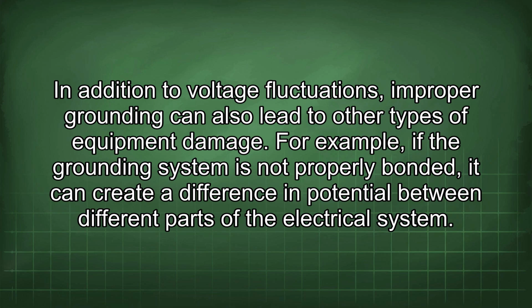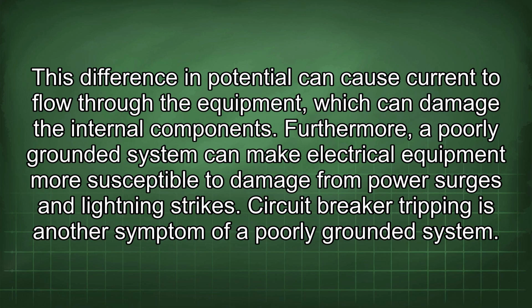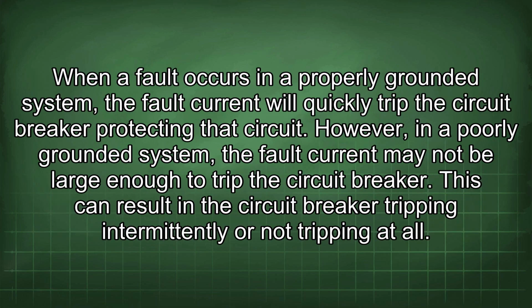For example, if the grounding system is not properly bonded, it can create a difference in potential between different parts of the electrical system. This difference in potential can cause current to flow through the equipment, which can damage the internal components. Furthermore, a poorly grounded system can make electrical equipment more susceptible to damage from power surges and lightning strikes. Circuit breaker tripping is another symptom of a poorly grounded system. When a fault occurs in a properly grounded system, the fault current will quickly trip the circuit breaker protecting the circuit. However, in a poorly grounded system, the fault current may not be large enough to trip the circuit breaker. This can result in the circuit breaker tripping intermittently or not tripping at all.